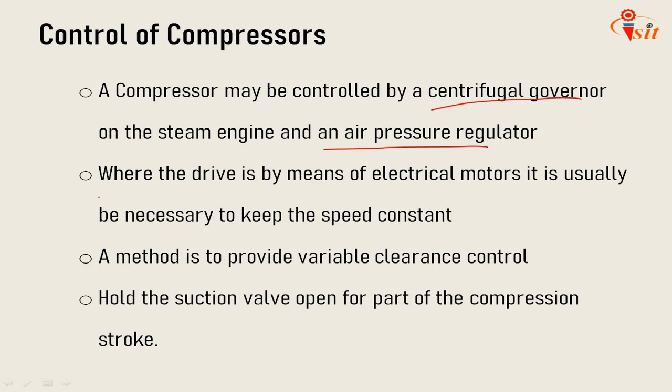Second is where the drive is by means of electrical motors. It will usually be necessary to keep the speed constant. It may be inevitable with synchronous motors, and then some unloading device may be used to blow low pressure air off to the atmosphere. Now by artificially obstructing the low pressure intake and thus lowering the intake pressure in addition to the mass aspirated, the temperature of the delivery may be raised to a dangerous value at a high pressure ratio, and this method is therefore not to be recommended. So we are not using this method.